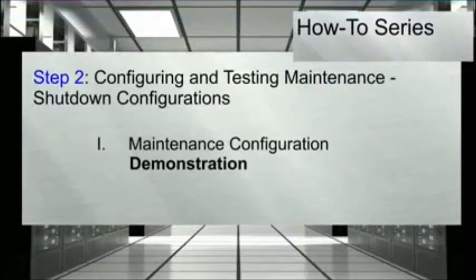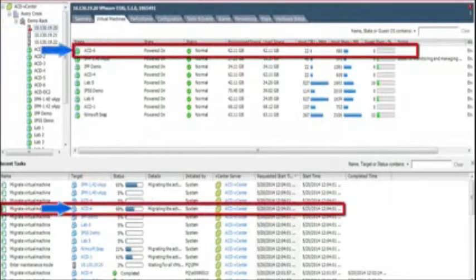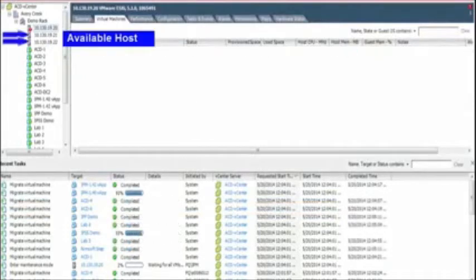The following is a demonstration of the maintenance mode configuration activated. The UPS supporting the host ESXi server has encountered a power event and the timer has met the threshold. A warning icon will appear beside the affected host as maintenance mode is activated. The virtual machines located on the host will begin to migrate to the other available hosts to remain active. As the VMs complete their migration, they are removed from the affected host. For example, let's watch the VM titled ACD-6. Once the migration is completed, you can see it disappear from the host folder. The result of the host being placed in maintenance mode shows an empty host folder with the VMs migrated into available hosts.